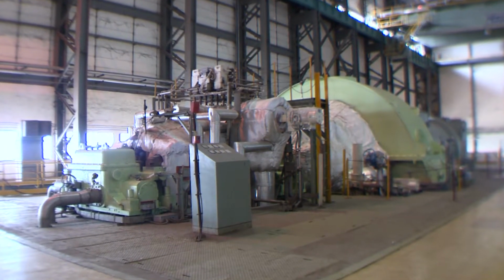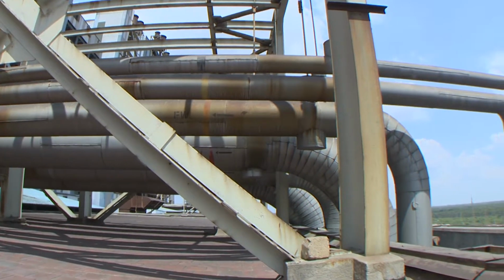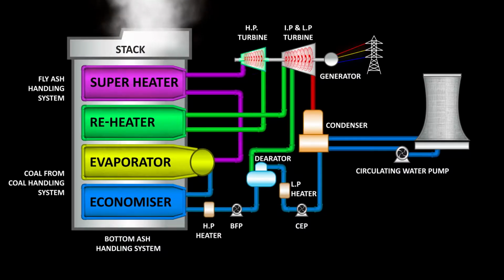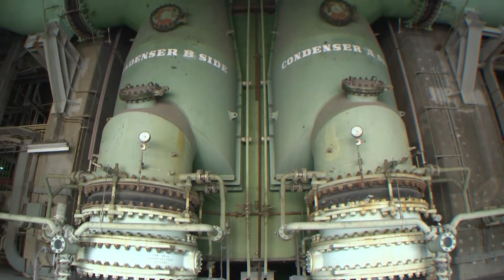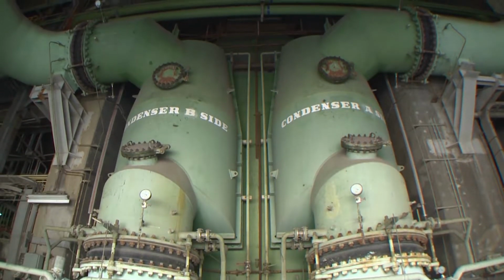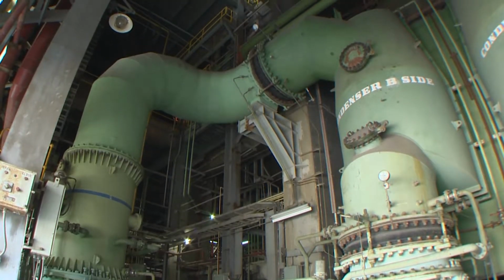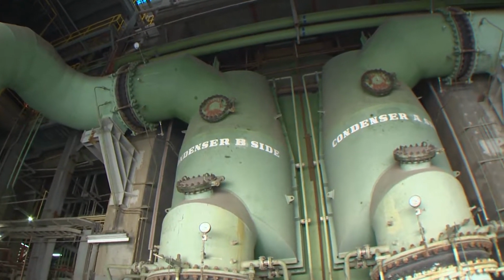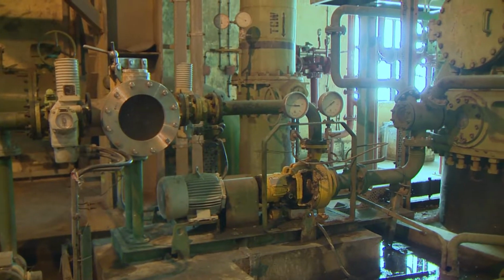The boiler supplies superheated steam to the HP turbine through main steam lines. After the work is done, the exhaust from the HP turbine reaches the reheater arranged in the boiler through cold reheat lines. The reheated steam is taken to the IP turbine through the hot reheat line. Then the steam expands in the IP and LP turbines. The exhaust from the LP turbine passes through the condenser where it is condensed. The condenser is surface type, single shell, rectangular, and 2 passes in construction. A sponge rubber ball type online tube cleaning system has been provided for condenser tube cleaning.